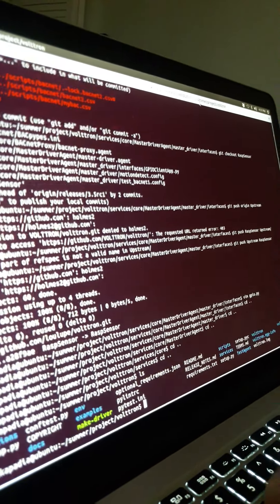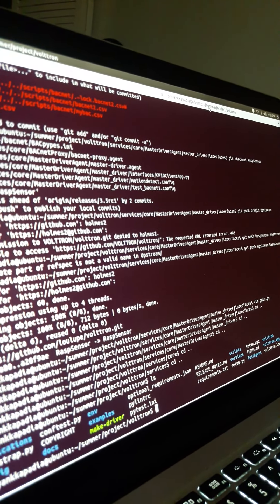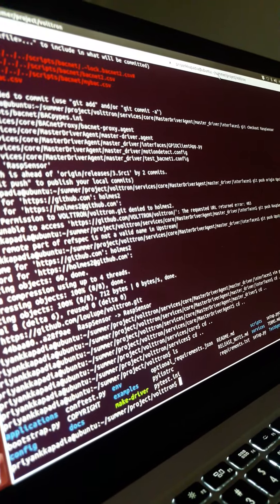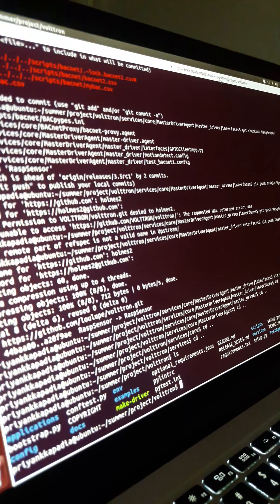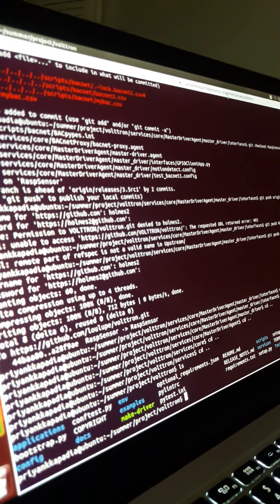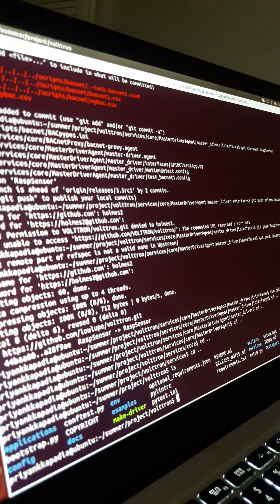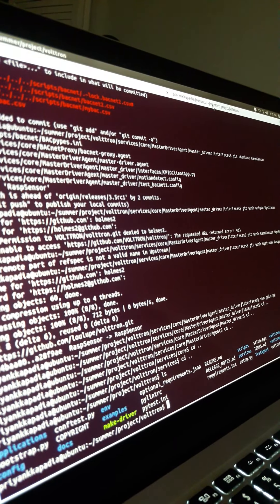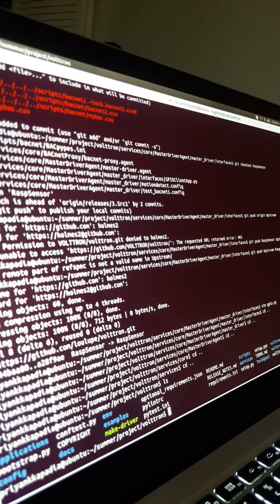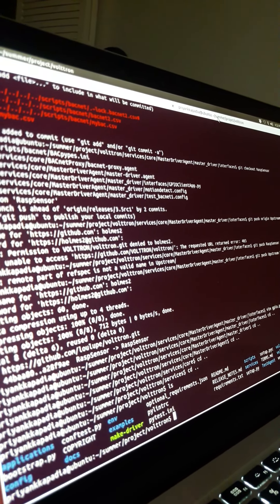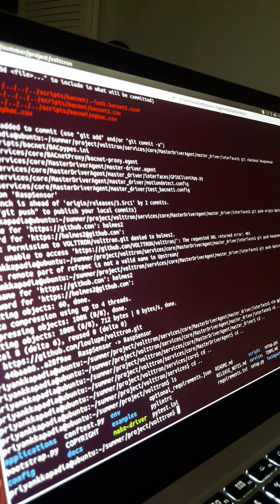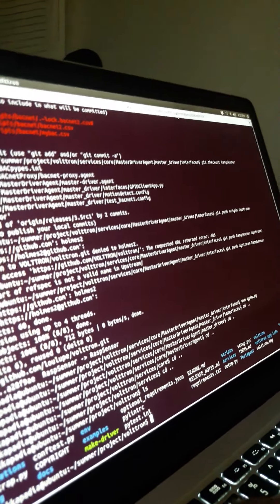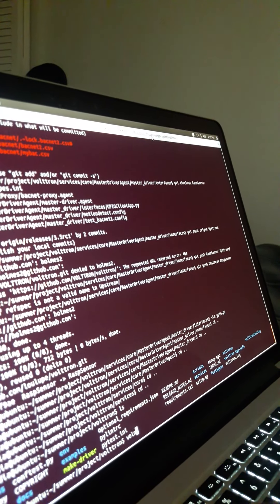VOLTTRON is made up of a lot of agents — whether it's a driver, historian, or a test agent, everything works as an agent and every agent has only one mode of installing. You call a pack install script. The first argument is where the agent is located — you give the folder of the agent. The second argument is the configuration file address of the agent. The third is you give the tag name of the agent. The tag name is decided by you and can be anything.